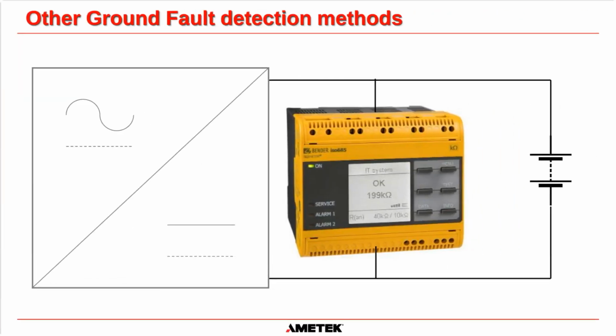And there's one other way. There's probably lots of other ways actually, but there's one other way that I know of to monitor ground fault circuits that is slightly different. It doesn't use a potential divider system. What it actually does is it injects a voltage between the positive and ground and the negative and ground, and then it uses calculations to work out what the insulation resistance is between those points.